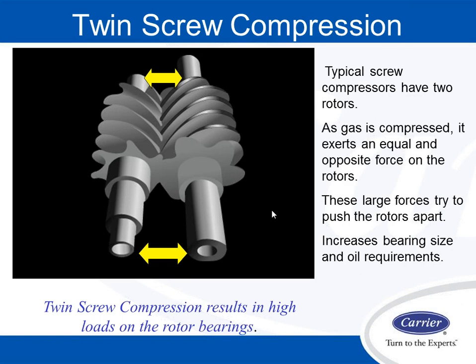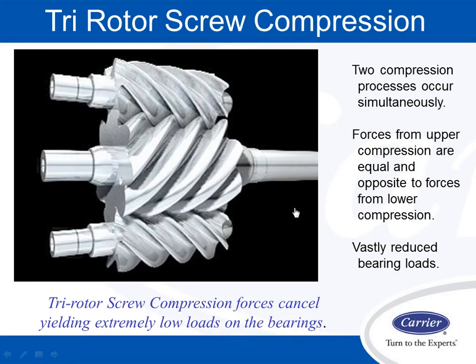If you look at the way a traditional twin screw compressor works, I have refrigerant that is basically passing through this twin rotor, and it is actually forcing that rotor apart. The typical twin screw is actually longer, so there's a little more slop in it, and as you have slop, you get inefficiencies. Because of those forces that are basically forcing the rotors out, we have huge bearing loads, and when we have huge bearing loads, we have a lot of oil that we have to lubricate, and as we have more oil to lubricate, we lose efficiency in the machine itself. So what Carrier did is we basically have what we call the tri-rotor screw compressor, and with the tri-rotor screw, we basically have forces that cancel both axially and radially.